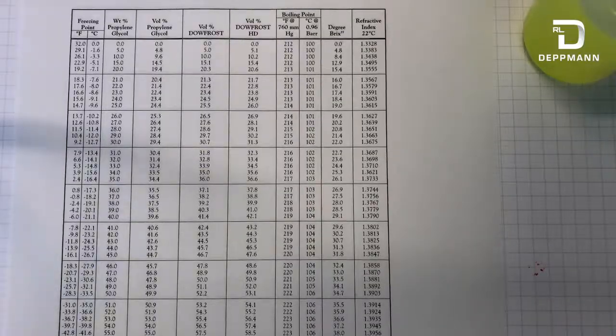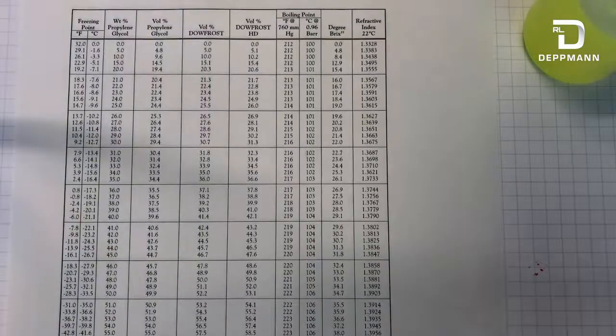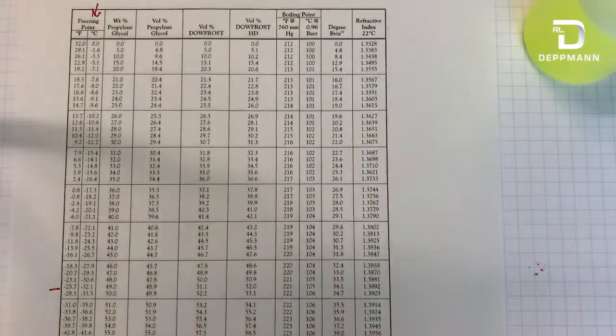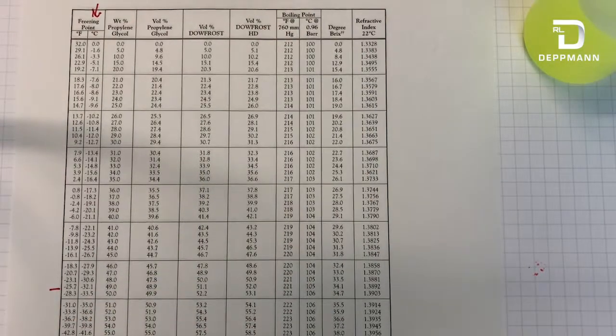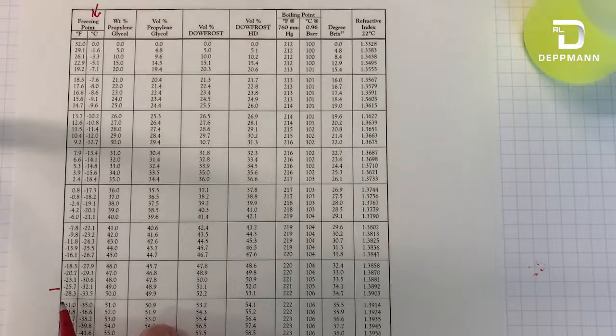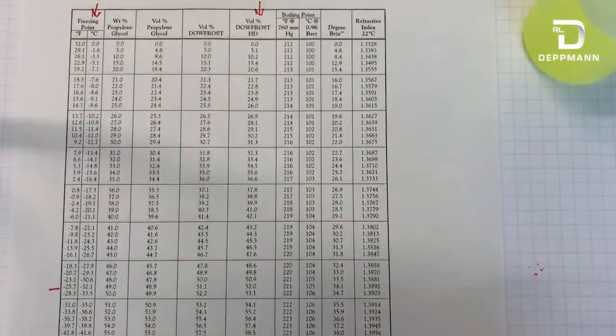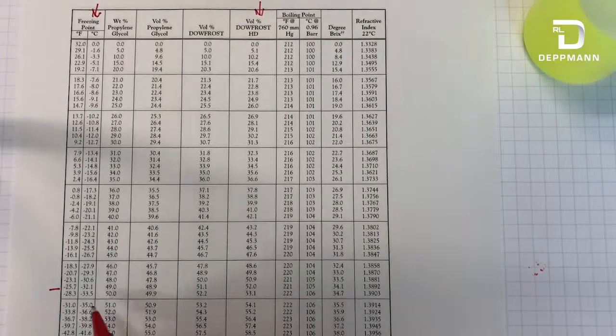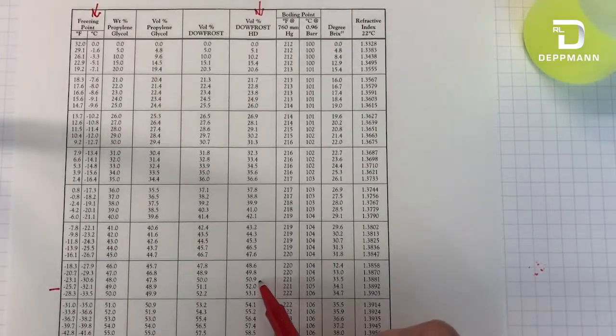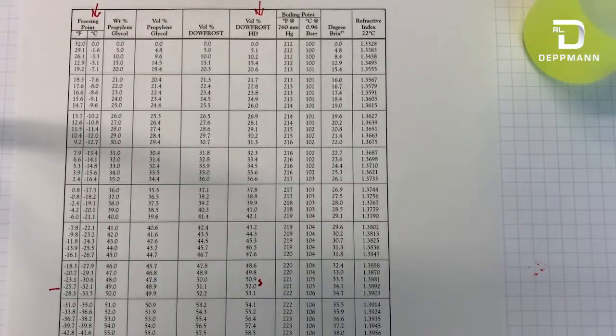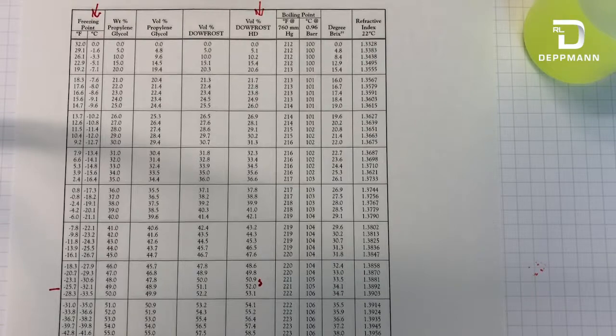After using the meter, I was able to determine my freeze point was right around negative 25 degrees Fahrenheit. I'm looking at the column for DOWFROST HD propylene glycol and based on this information, I'm right around 50 percent concentration. For my particular system, it was designed around 50 percent, so I am in good shape.